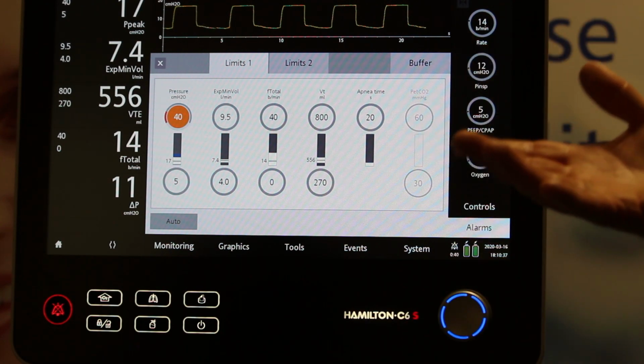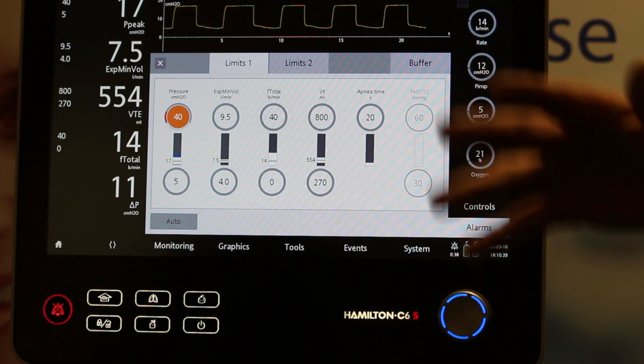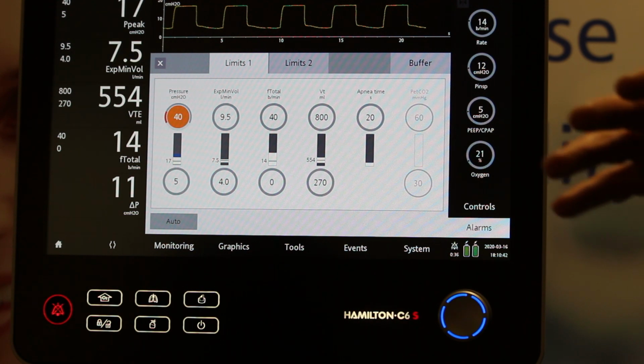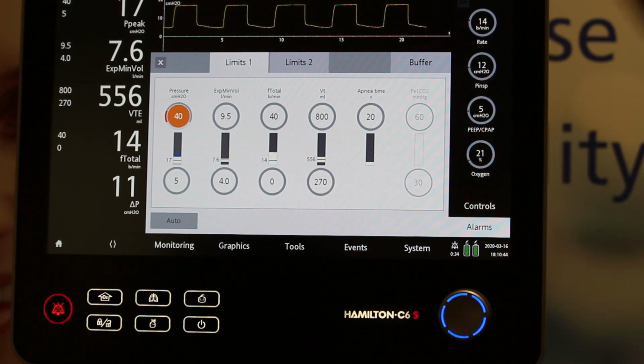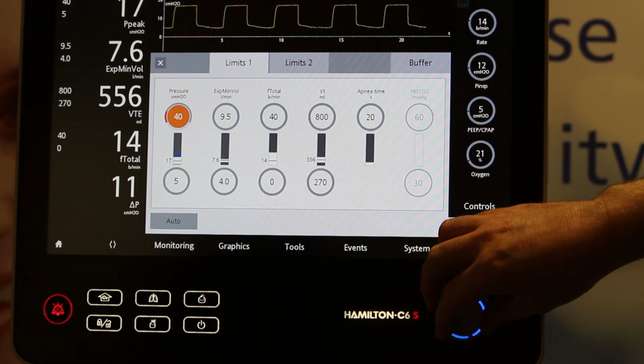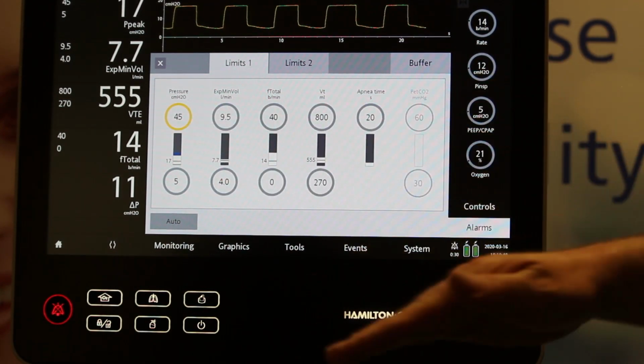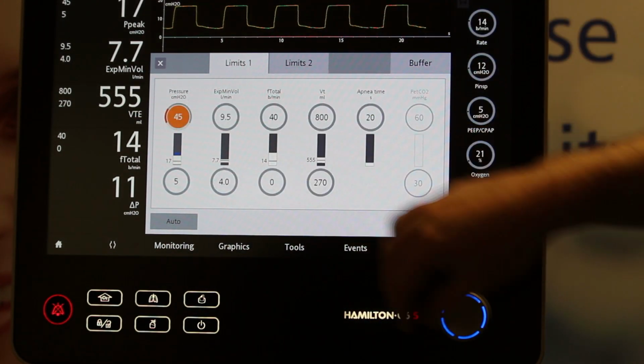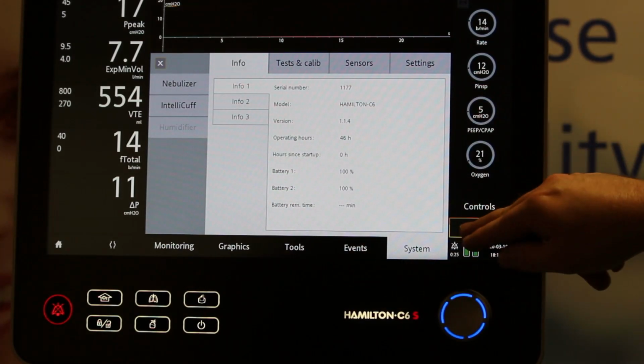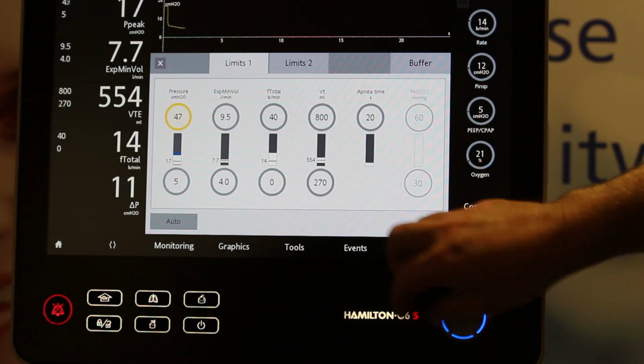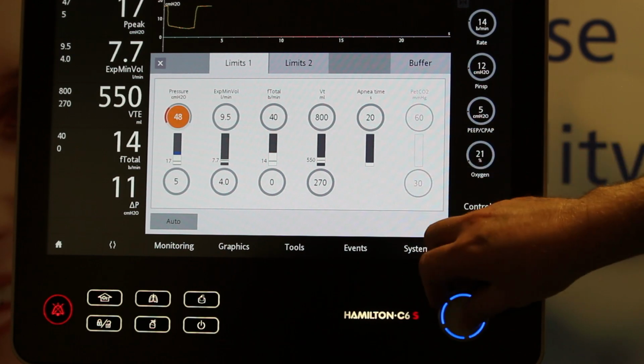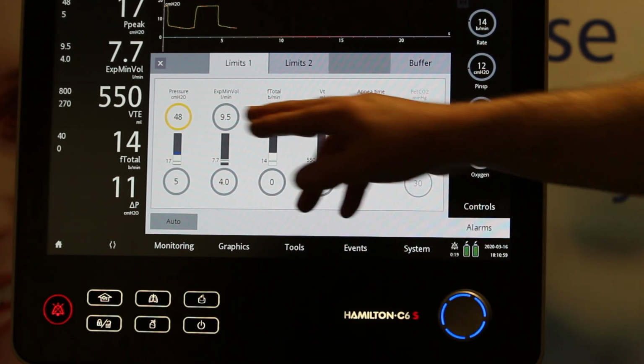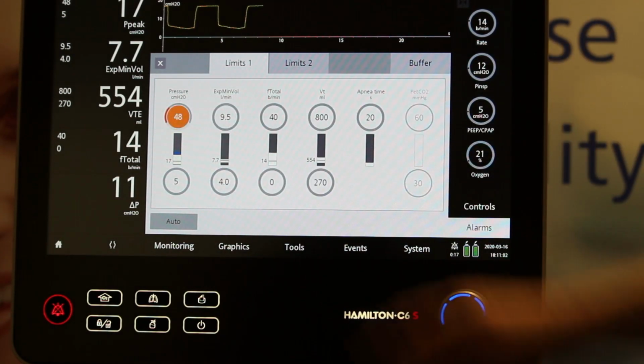So if you've got airway pressures coming up to 30 or rising to 30, the ventilator will start to restrict the breaths. And if you're happy for airway pressures to rise into the 30s, if you dial up your Pmax, so I dial to 45, my restriction lifts up to 35, or if I dialed it up to 48, my restriction would lift to 38, and so on. Always 10 centimetres of water below what your Pmax is set at.